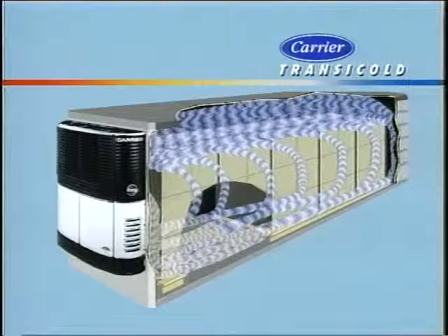Start-stop is used for products that are not sensitive to minor temperature changes and that do not require continuous airflow around the product. To change this to start-stop, press the start-stop continuous key once. The continuous run light will go off and the start-stop light will come on. The Message Center will show start-stop mode selected. Additional information is available on the best times to use start-stop or continuous run operation in the operator's manual.